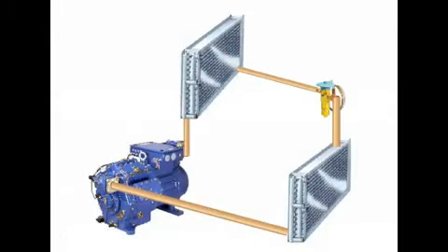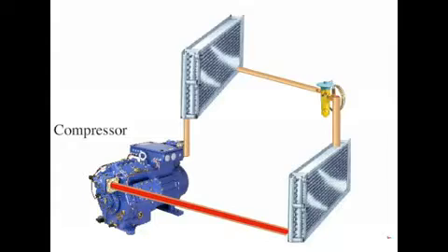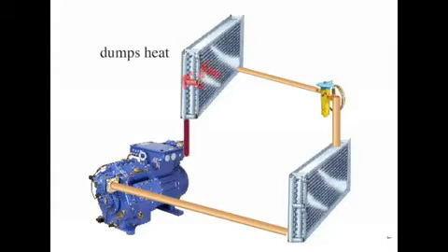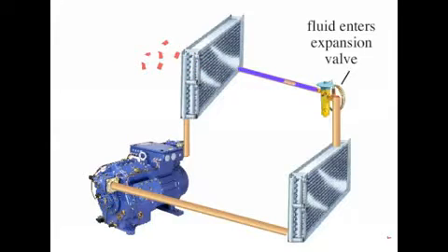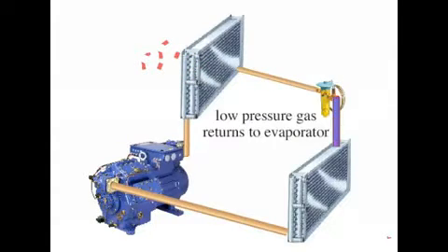In the mechanical vapor compression system, the refrigerant circulates in a closed loop through a series of components. The refrigerant liquid enters the evaporator, found inside the refrigerated space, and transforms to gas as it absorbs heat from the surroundings. A compressor takes the low-pressure vapor and converts it to high-pressure gas, with a vapor-liquid equilibrium temperature higher than that of the outside surroundings.